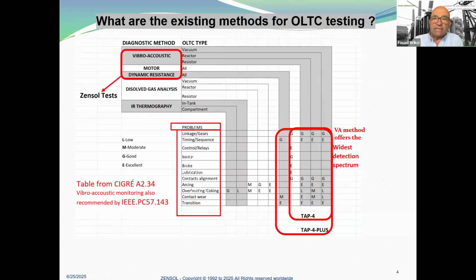So what are the existing methods for OLTC testing? This table shows a brief comparison between the 5 existing methods presently available in the industry for OLTC maintenance. The Vibroacoustic method offers the widest detection spectrum. This table is from Cigré, and Vibroacoustic is also recommended by IEEE. For example, you can see that overheating and coking is marked low for Vibroacoustic, but is marked excellent for timing, transition, and arcing. As you can see, the Vibroacoustic method offers the widest detection spectrum since it is able to detect, at the earliest stages, problems with the brake, selector, lack of lubrication, contact wear, and many other problems related to OLTCs.